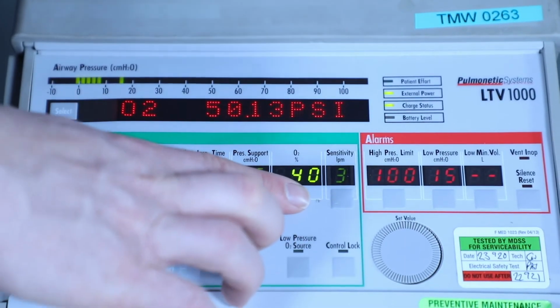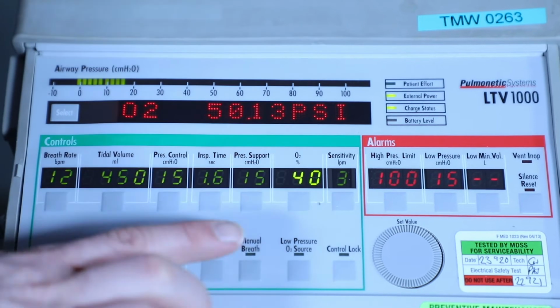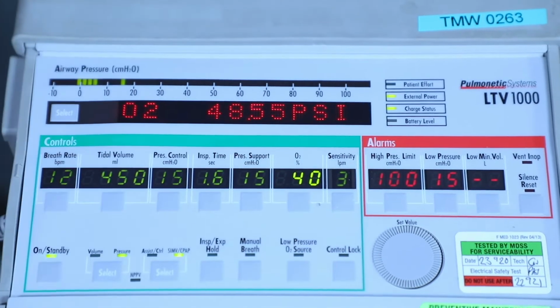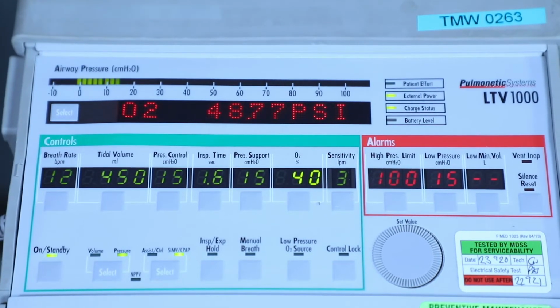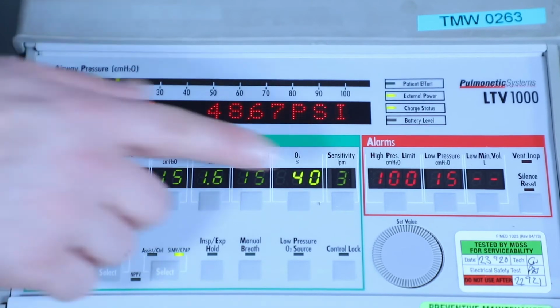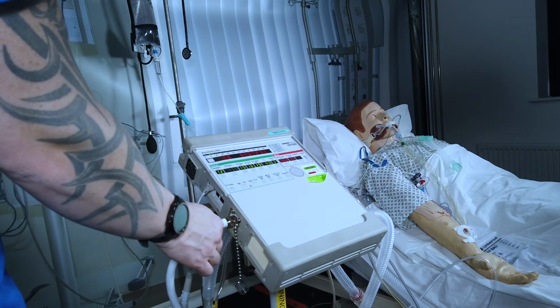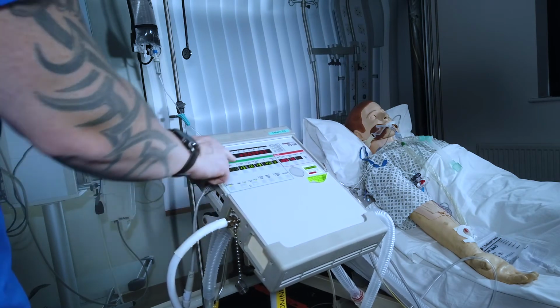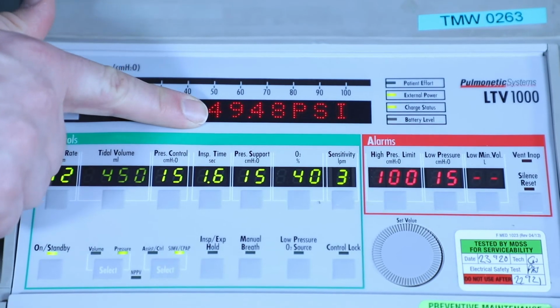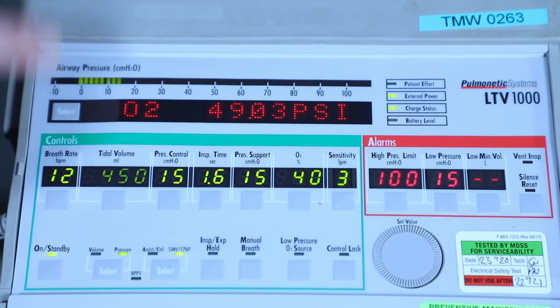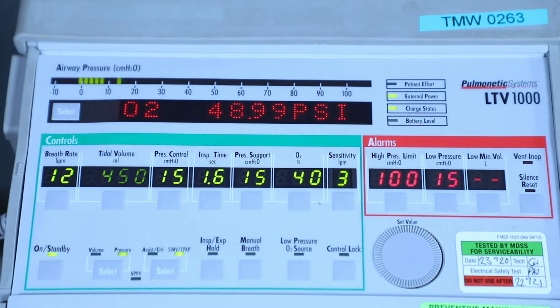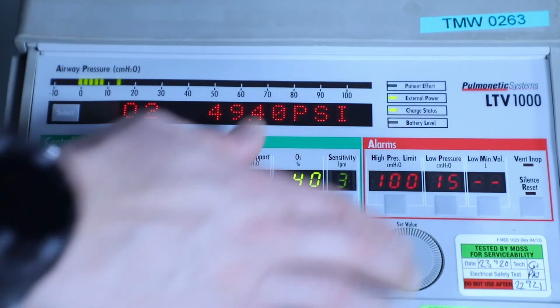This allows us to put a bit more pressure on the hose. Once we've got this running at a higher percentage of oxygen, we can give a bit of a wiggle test just to ensure that the number doesn't fall below 40. Once we're happy with the pressure in the system, we can put the oxygen back down to 21%.